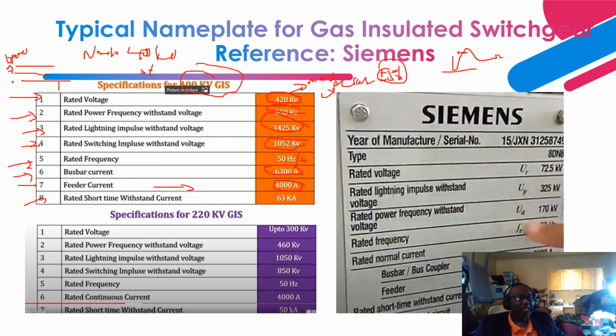Next is the rated short time withstand current, right? Short time is either 1 second or 3 seconds. That is the symmetrical short circuit current. So that's how much short circuit capability it can withstand when a short circuit occurs in each compartment or the overall compartment of the GIS.